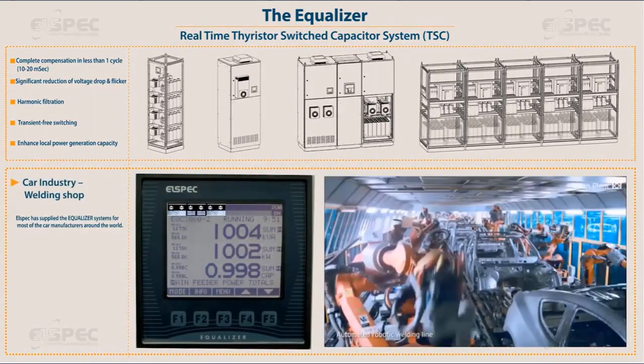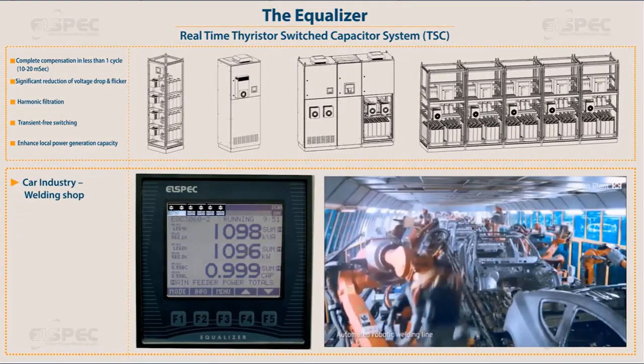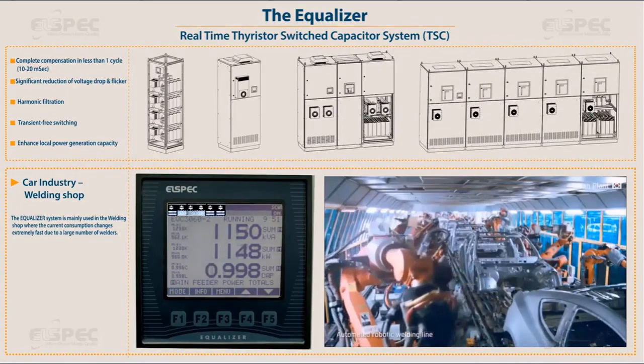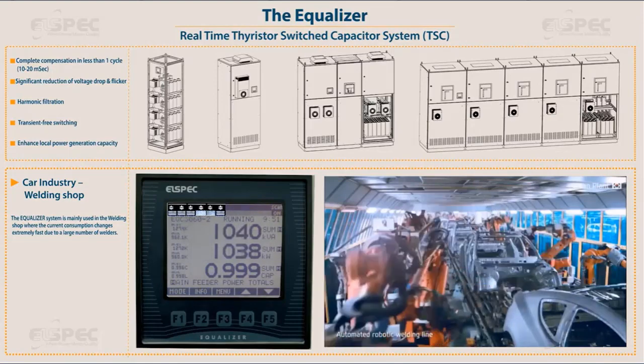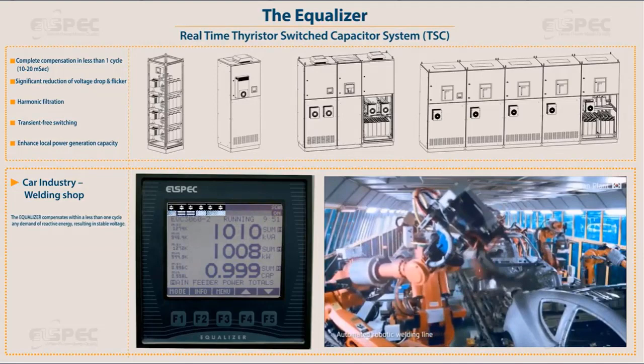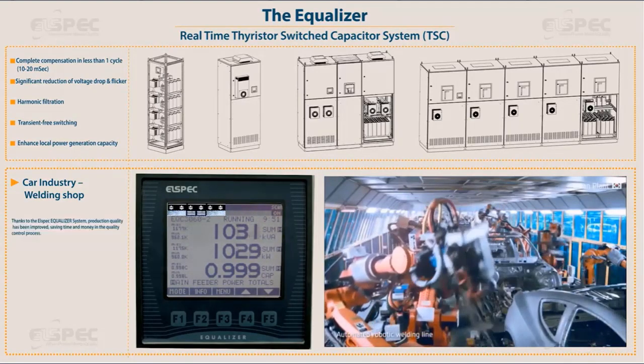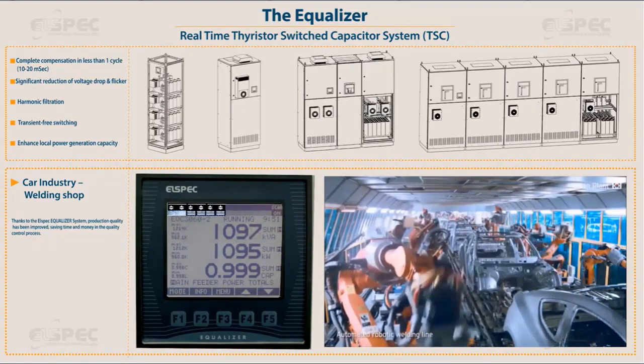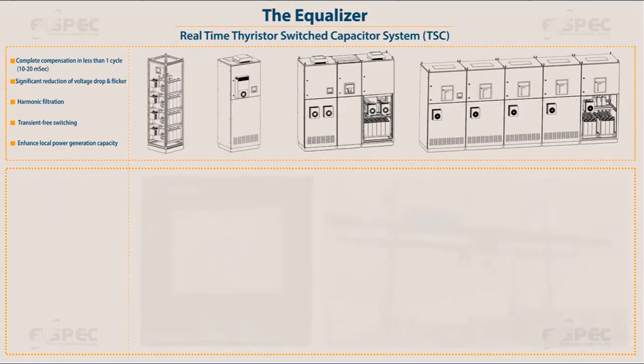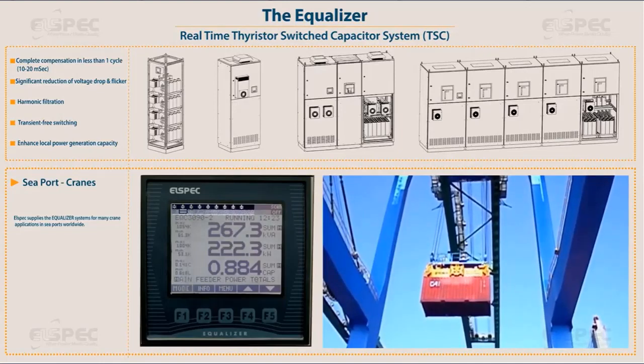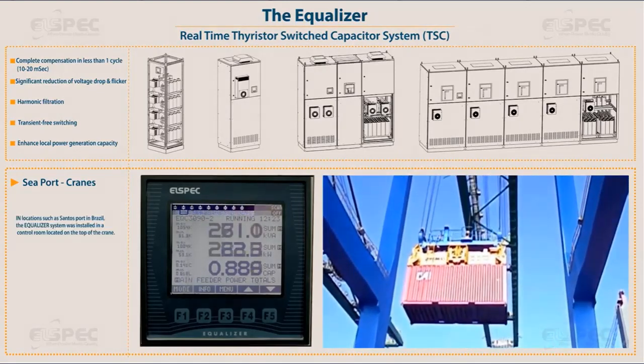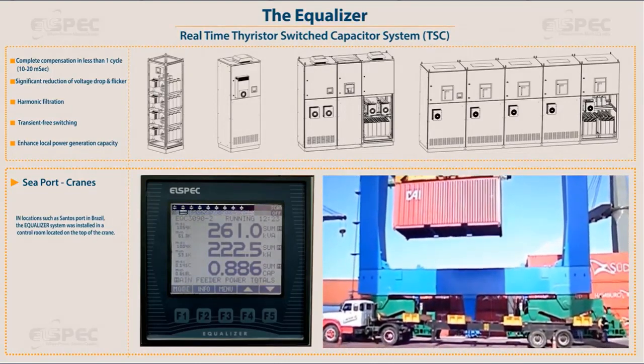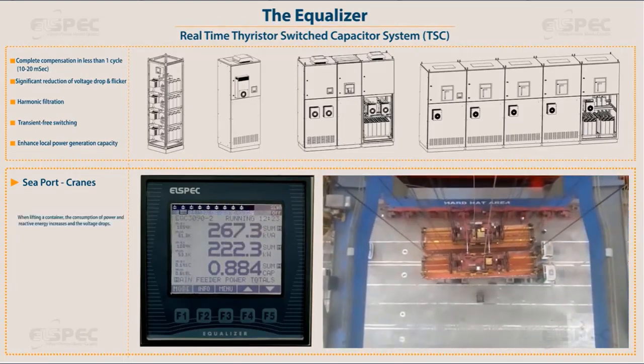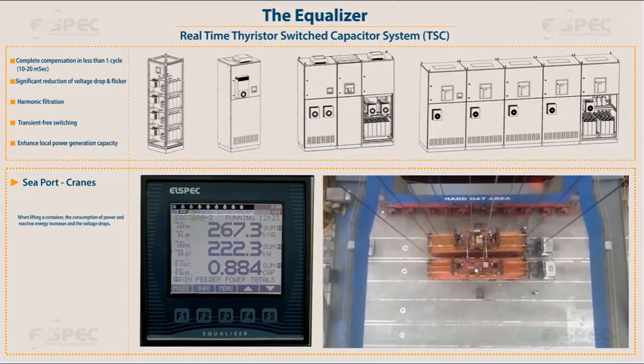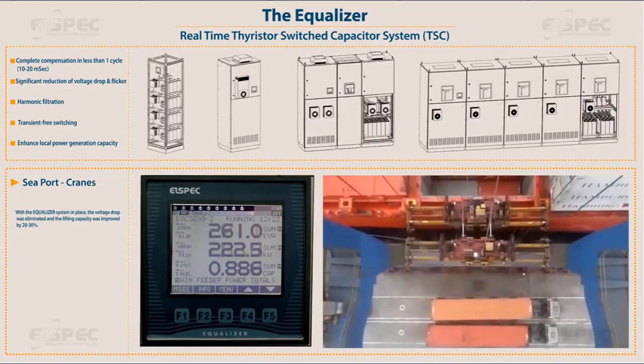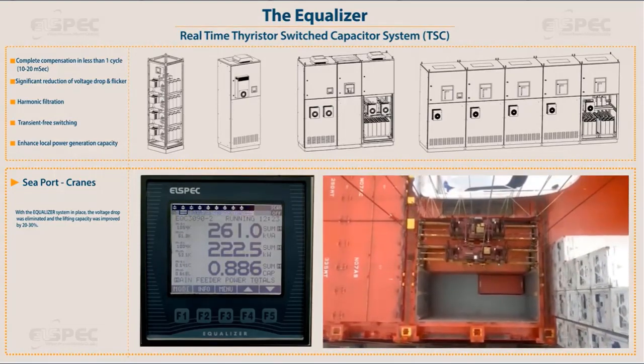ELSPEC has supplied the equalizer systems for most of the car manufacturers around the world. The equalizer system is mainly used in the welding shop, where the current consumption changes extremely fast due to a large number of welders. The equalizer compensates within less than one cycle any demand of reactive energy, resulting in stable voltage. Thanks to the ELSPEC equalizer system, production quality has been improved, saving time and money in the quality control process. ELSPEC supplies the equalizer systems for many crane applications in seaports worldwide. In locations such as Santos Port in Brazil, the equalizer system was installed in a control room located on the top of the crane. When lifting a container, the consumption of power and reactive energy increases and the voltage drops. With the equalizer system in place, the voltage drop was eliminated and the lifting capacity was improved by 20 to 30%.